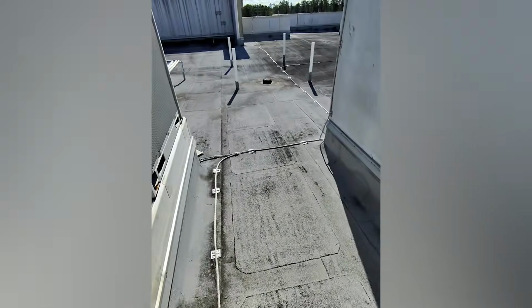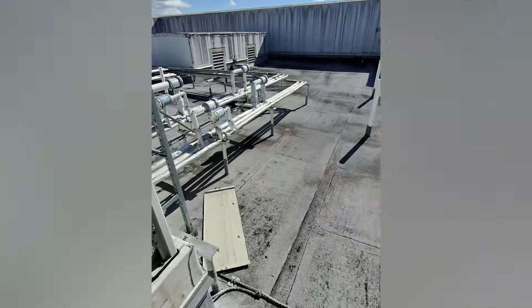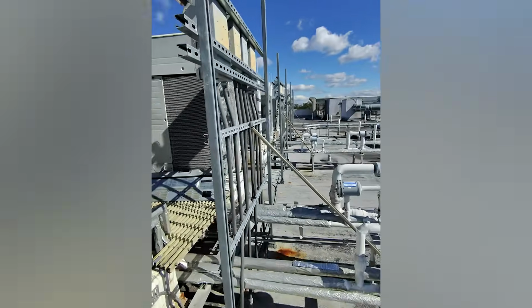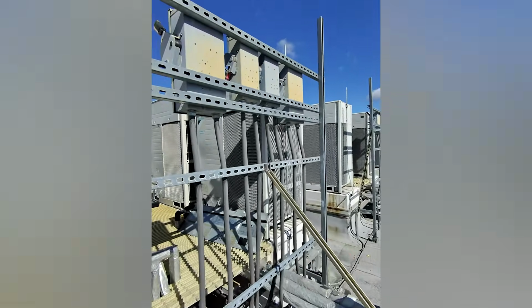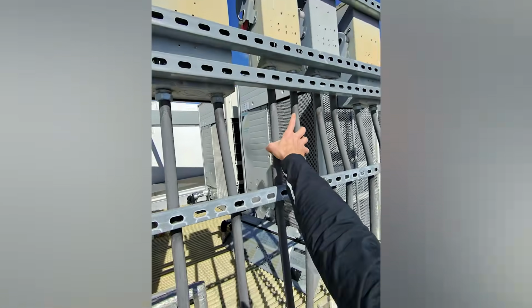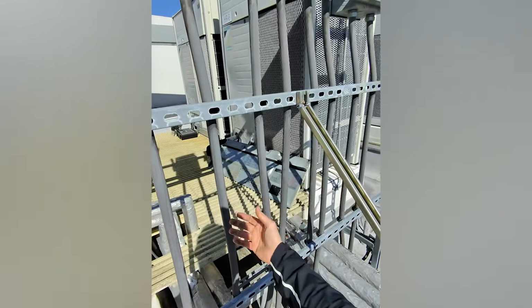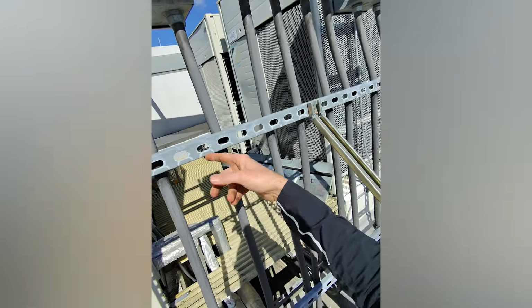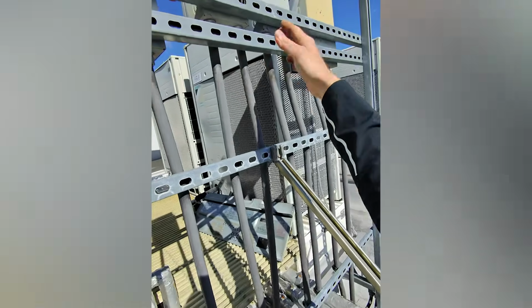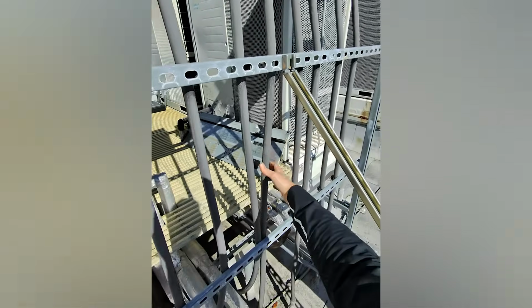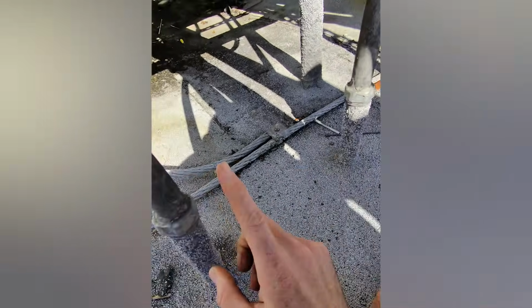So we follow it down and over, walk around the corner here. You're going to notice this is our disconnect. Left wire goes over to our unit, which is not sealed inside the unit, but water's not going to come up, go to the connections and come down. It's this one here. And if we go down and take a look, you're gonna see the rings they used, they silicone them.